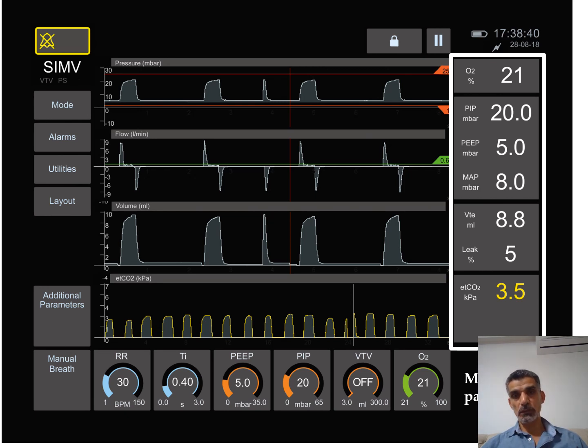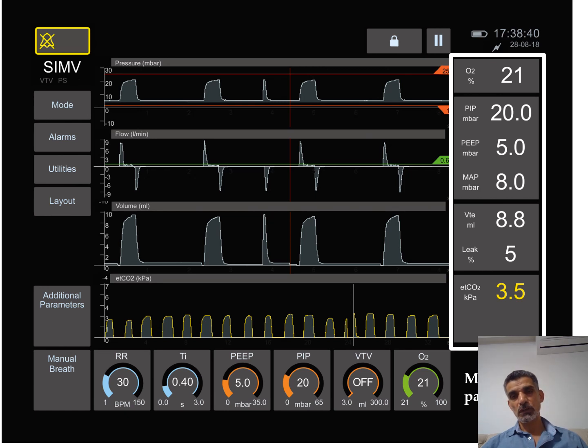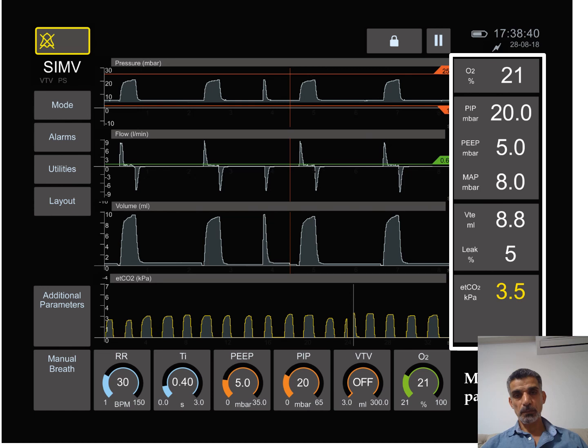This is we set 20, but this will tell us how much actually PIP is going to the baby, also how much PEEP, and also the MAP which is the mean airway pressure, which is the pressure under the curve reaching the baby. It's composed of the PEEP, the PIP, and also the rate in addition to the inspiratory time.